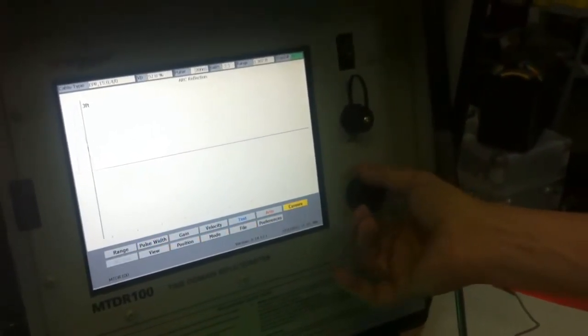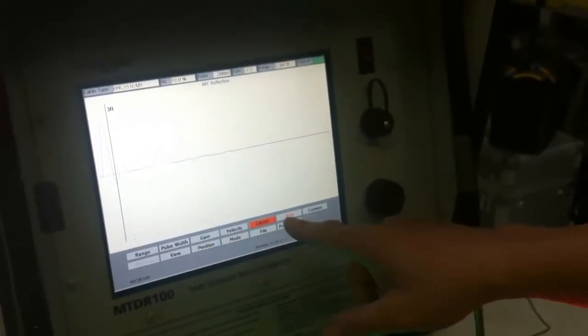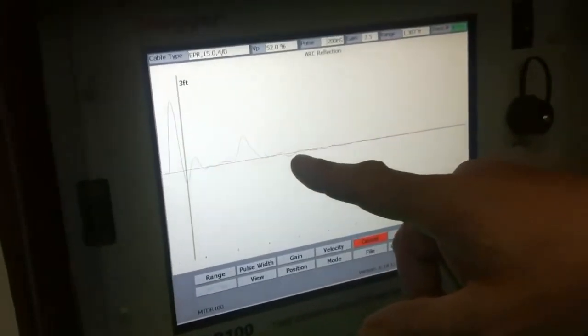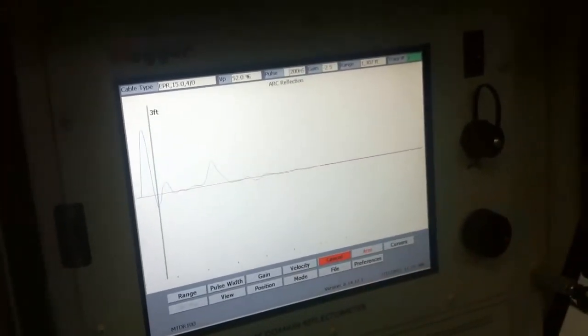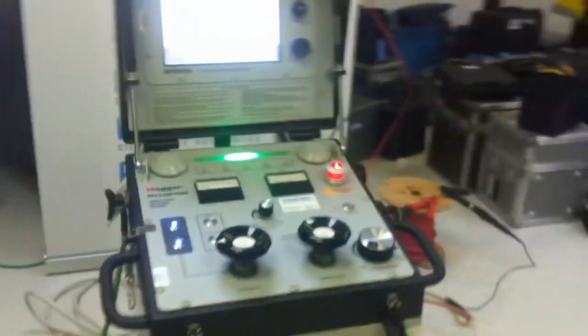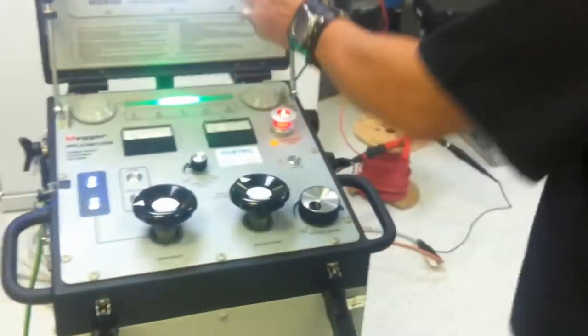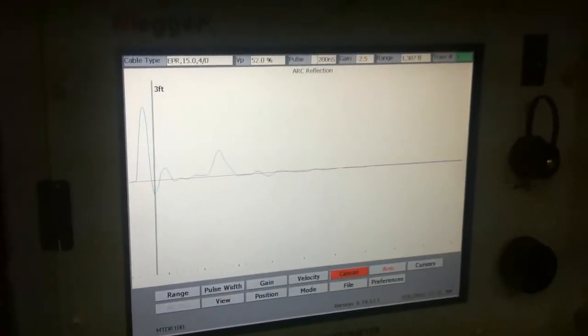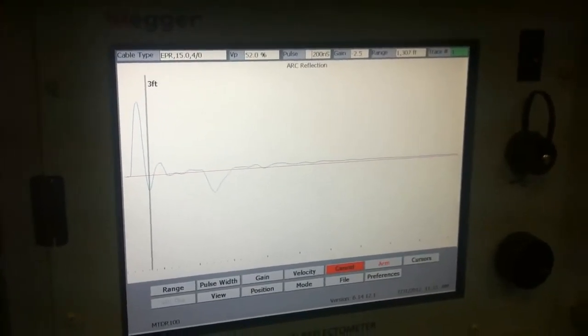As I come over here to test, notice that by rotating this knob, I can change any of my selections. By pressing, I can activate. So I've just run a TDR test. Here I can see the end of the cable, I can prove that it's the end of the cable by applying a shunt or a short circuit to that point. And just excuse me while I find a tool to apply a short circuit. An open end of cable or open circuit will be an upward reflection. A shorted end or grounded will be a negative reflection.